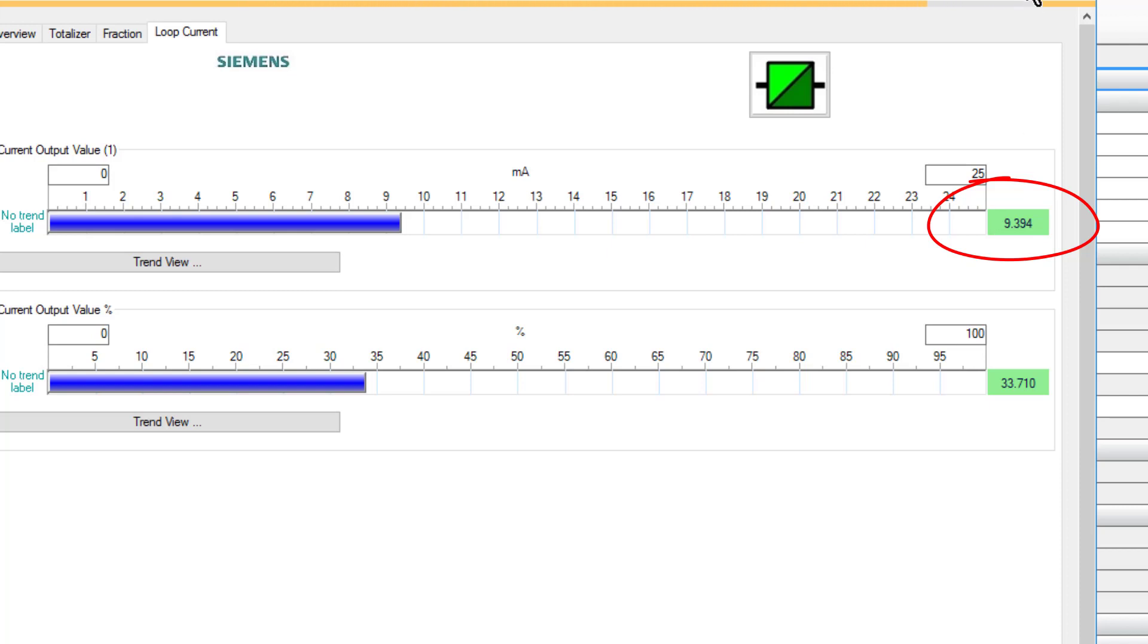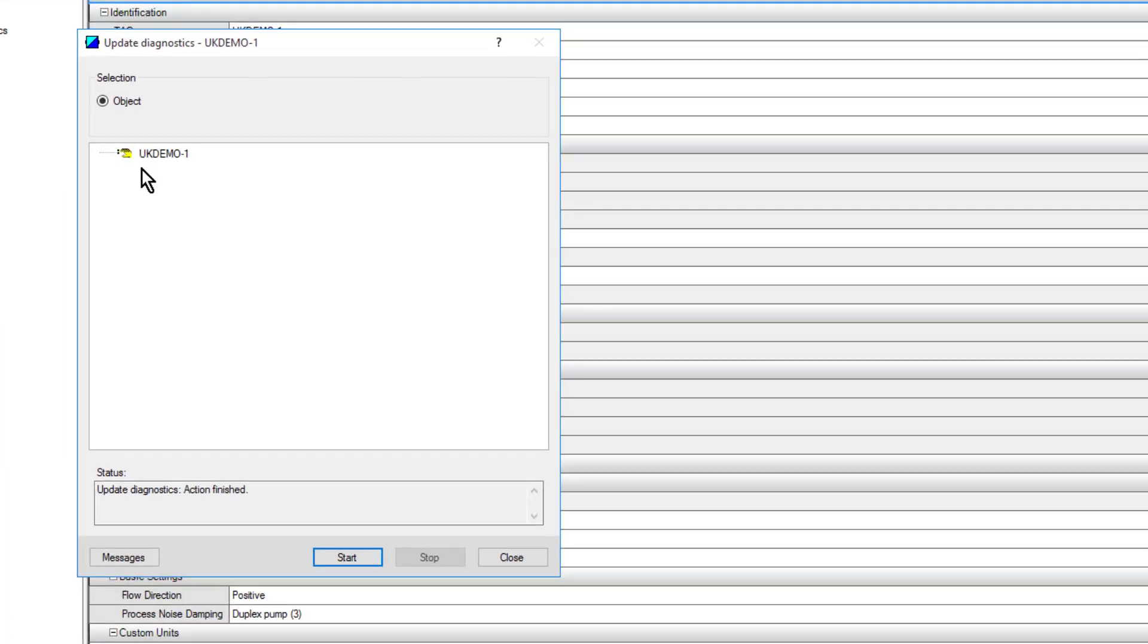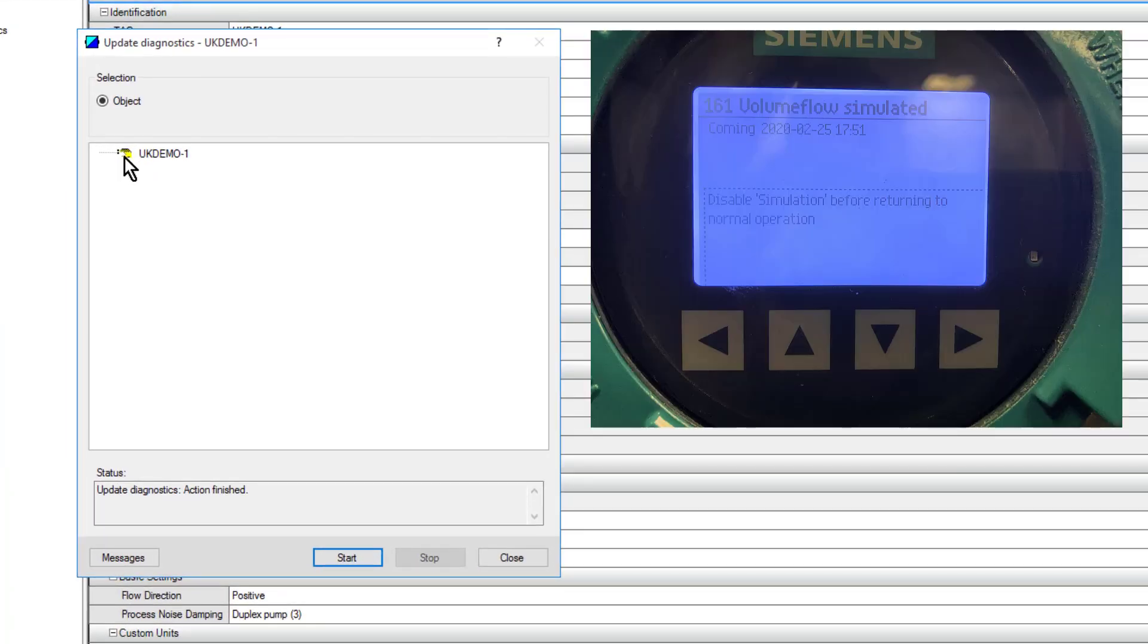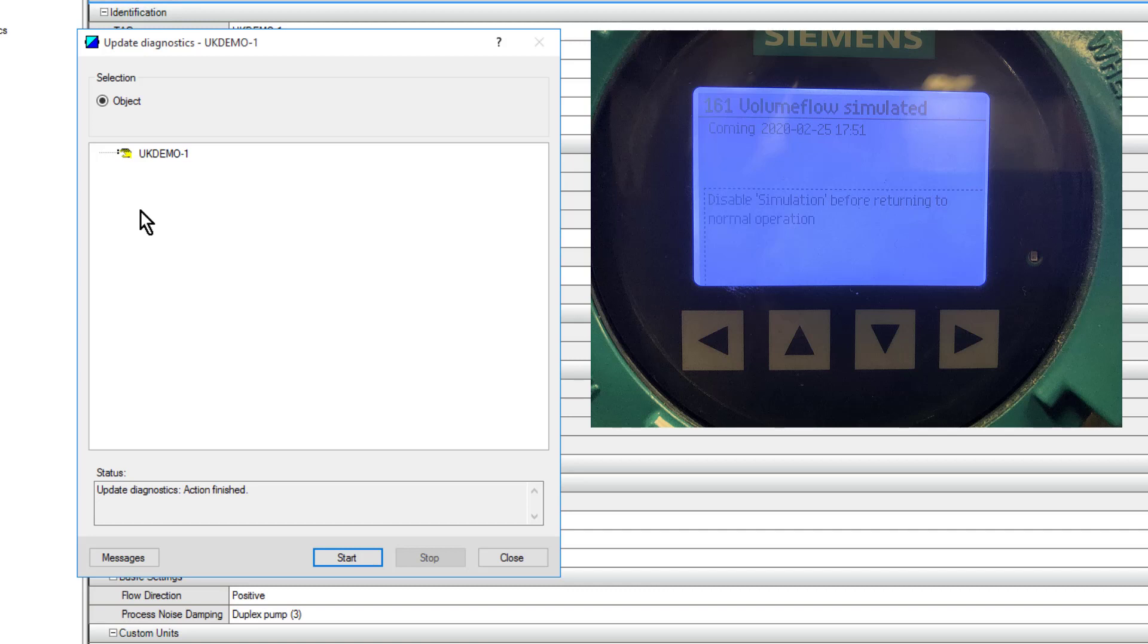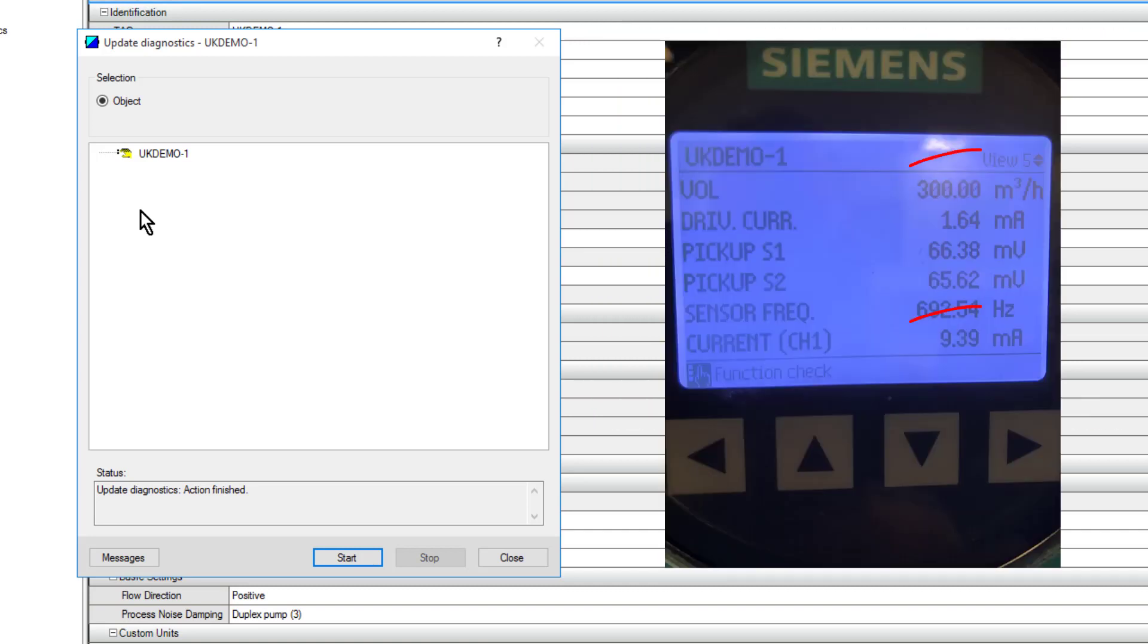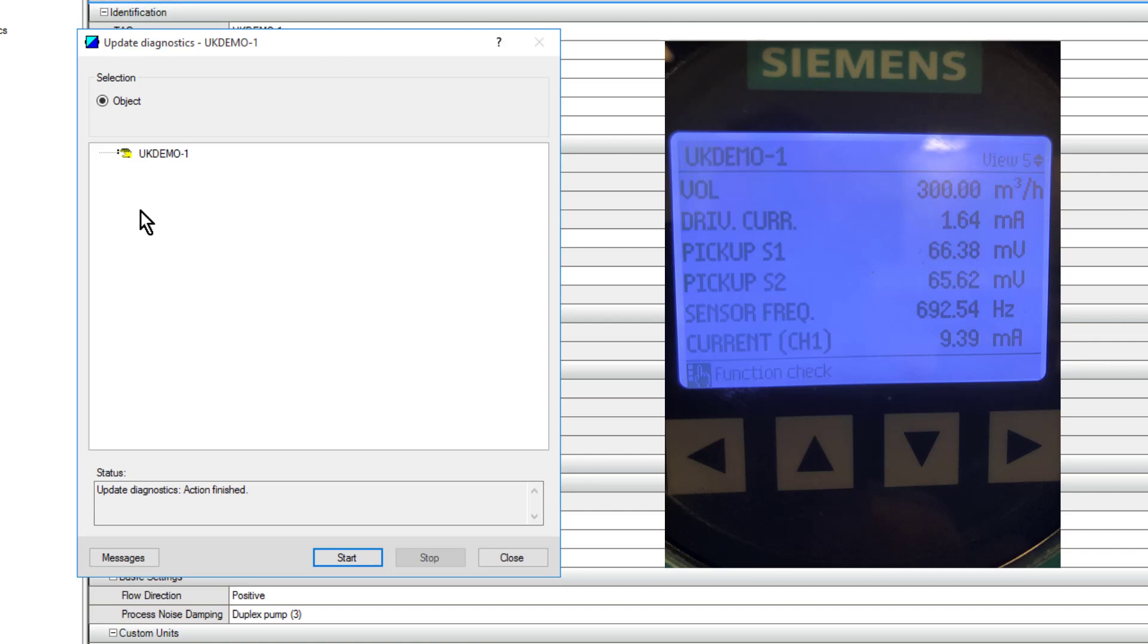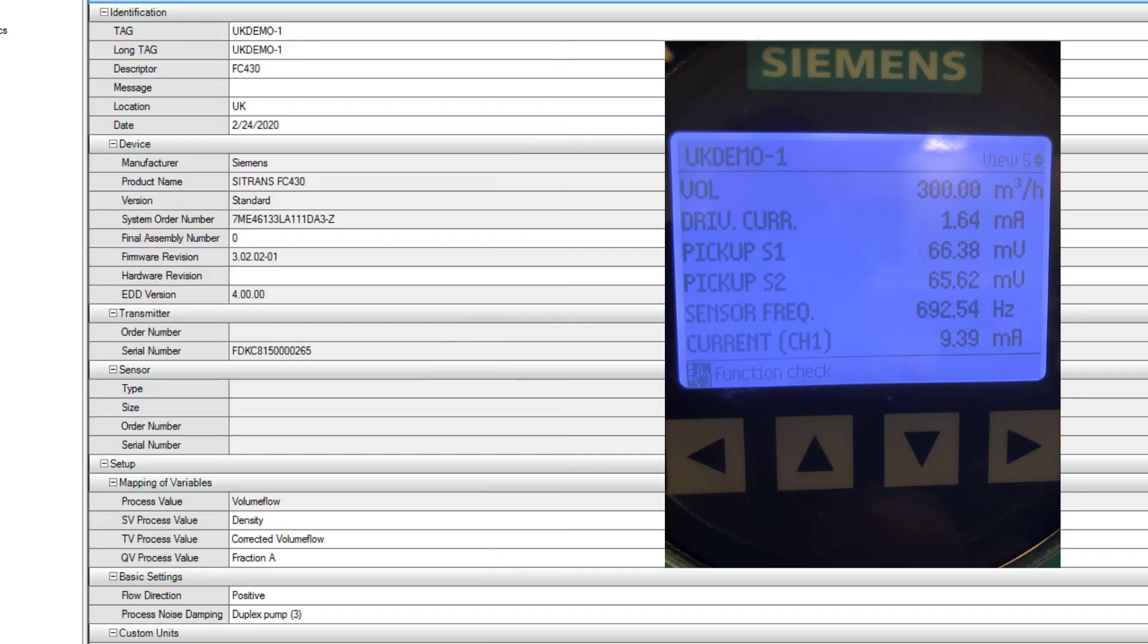It does a full simulation of what would actually happen with the screen. The screen will change value. The only thing you need to be wary of is you'll have a different symbol. You can see here the hand symbol is stating the unit is in simulation. This particular flow meter will stay in simulation until you tell it to stop simulating or you recycle the power. That's for any of the process values. If you want to do a long-term simulation for your loop test, then this is ideal.